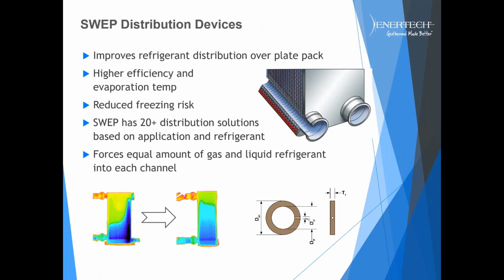So if we dive a little deeper into this braze plate, one of the things that SWEP is really known for in the industry is their distribution of the refrigerant and water through the braze plate. And that's really what they have perfected over the years. If you look at the two images there on the bottom, they get really good distribution of the refrigerant and water throughout the heat exchanger so you don't have cold spots. And that, of course, alleviates the freezing risk. And that's really what's most important about a water to refrigerant heat exchanger. So this design is really designed for water to refrigerant versus water to water, or maybe refrigerant to refrigerant. So the distribution device that they use is unique to SWEP and to Enertech.